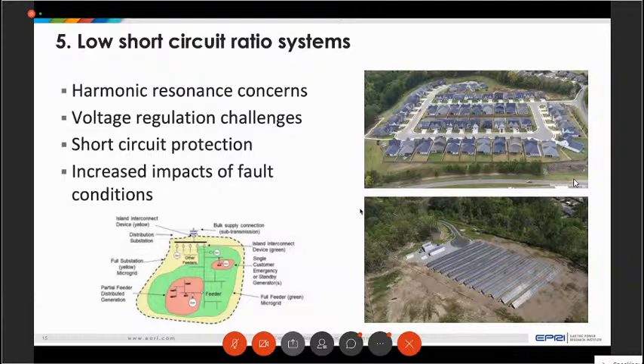The characteristics of those systems are that if we have a fault, or even a load variation, managing voltage becomes more difficult, because a load change has a bigger impact on voltage. Faults also have an impact over larger areas of the system.